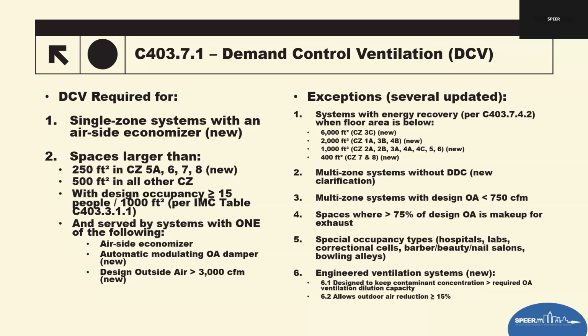So air side economizers, so automatically modulating outdoor air dampers. So the design outdoor air is greater than 3,000 CFM. These additions make the DCV applicable to more air handling units and rooftops. So there are exceptions updated by climate zone. So the exception for systems with energy recovery have new square foot thresholds based on climate zone. These are basically now universally lower and better aligned with energy recovery requirements.